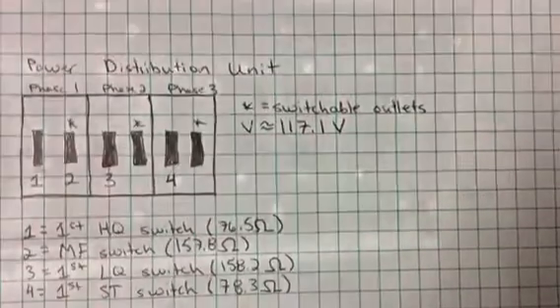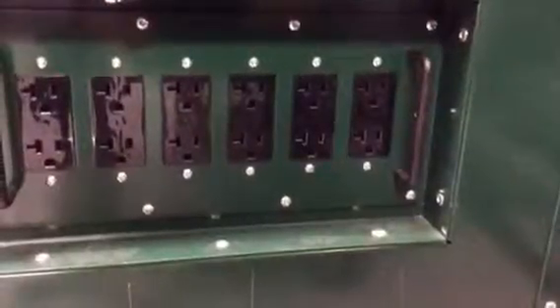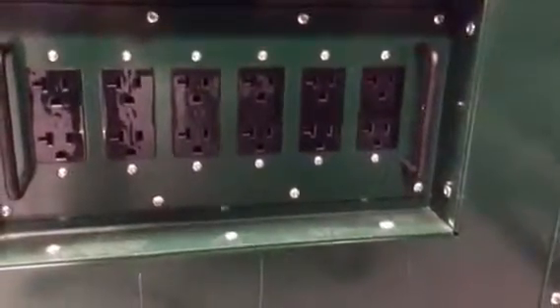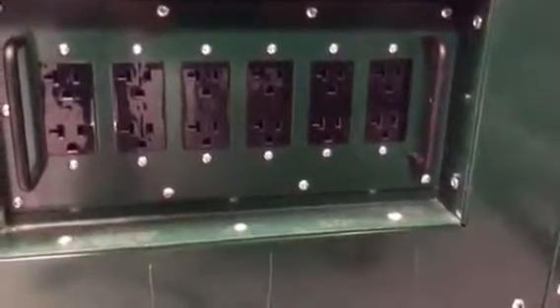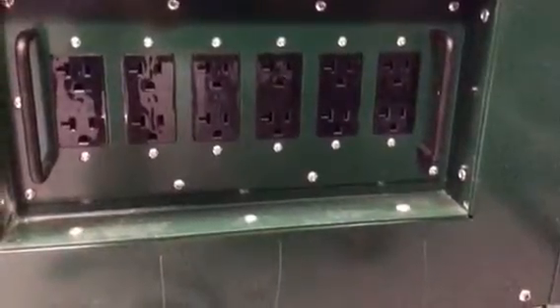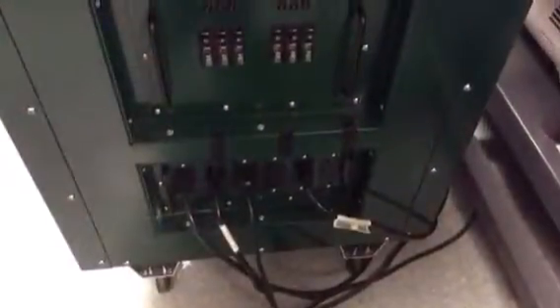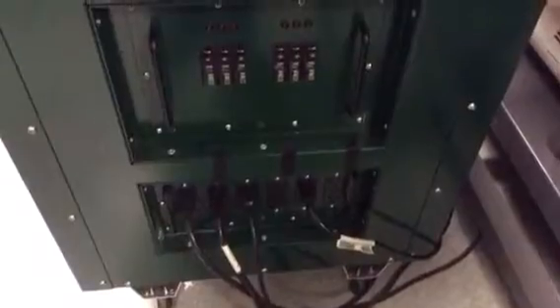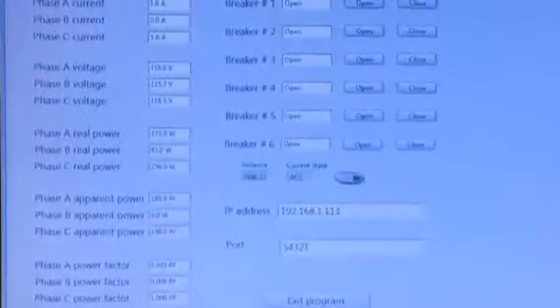The PDU has 6 sets of outlets, with one permanently tied to each phase and the other with the ability to switch the respective load to a different phase. As you can see on the PDU, the outlets marked by a strip of electrical tape above them have the ability to switch.